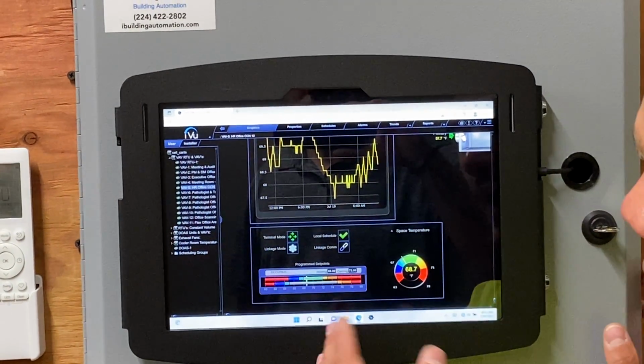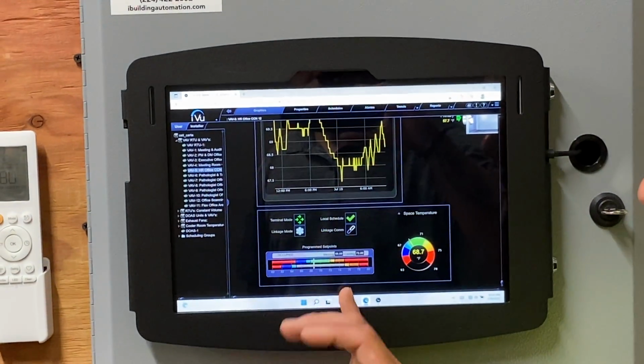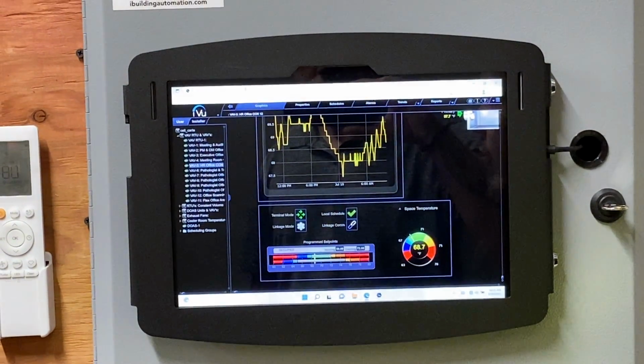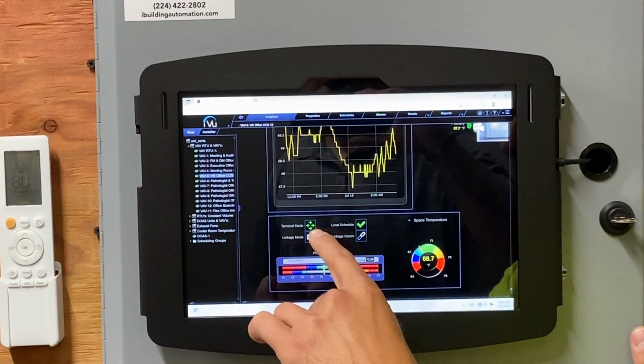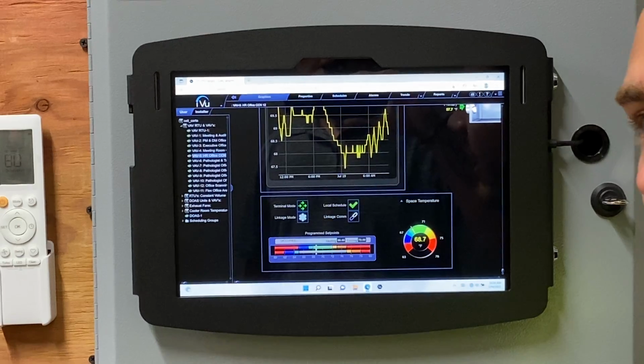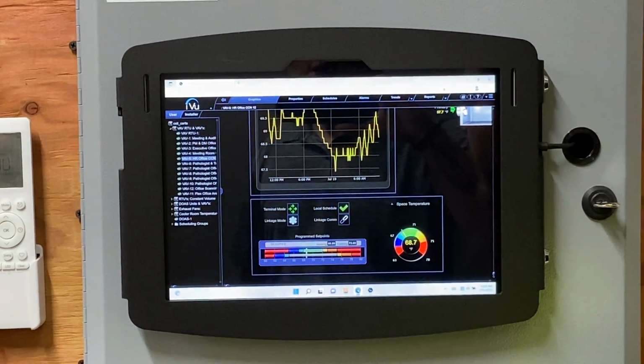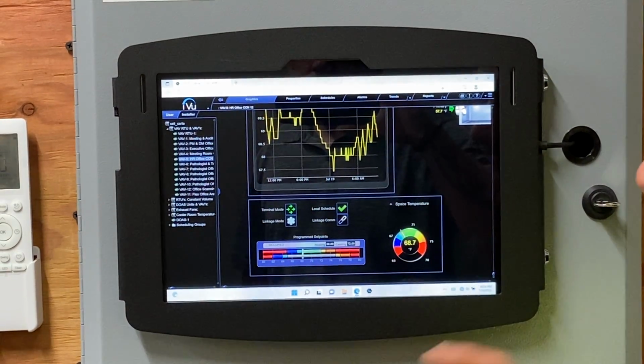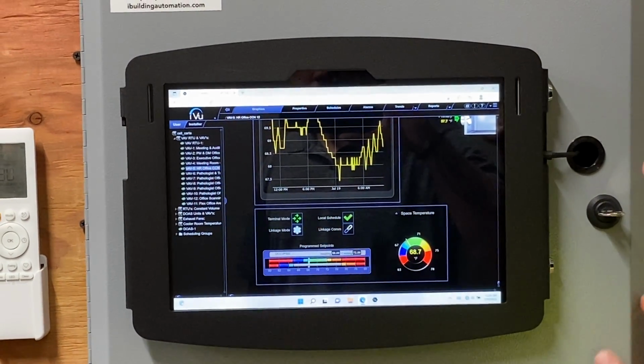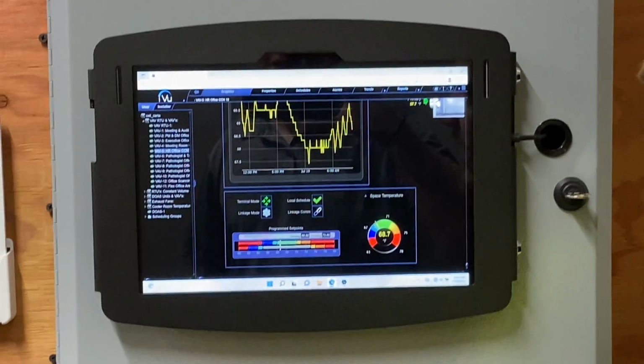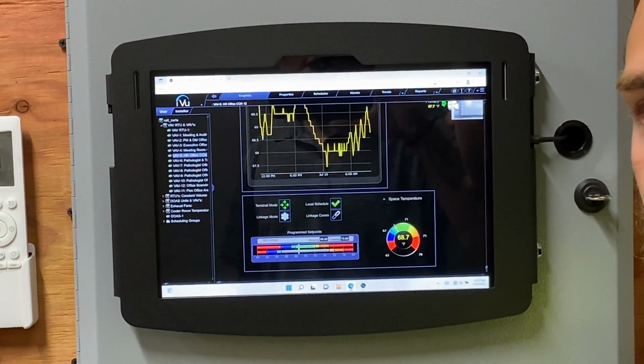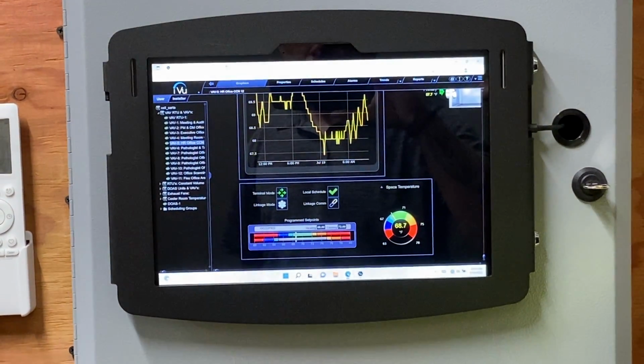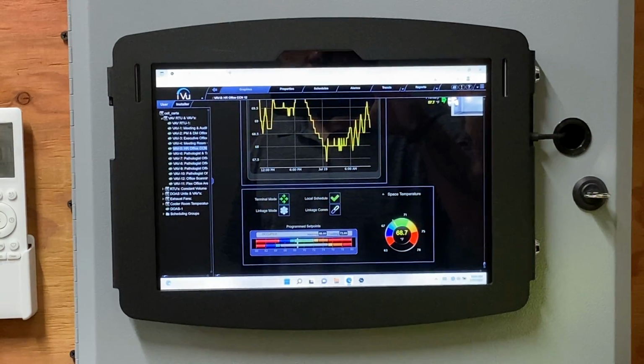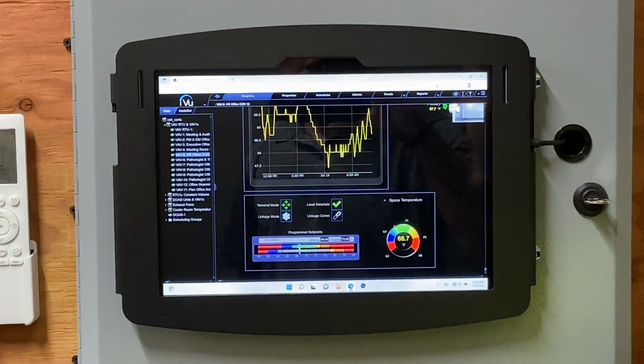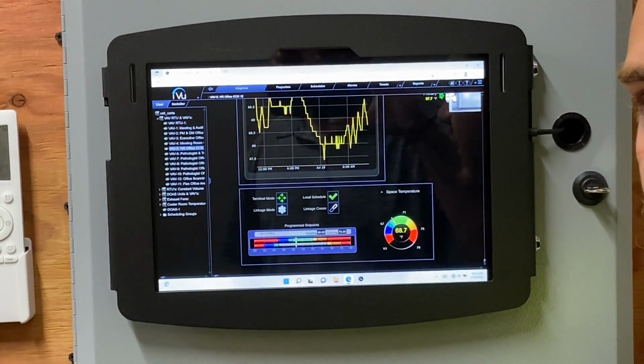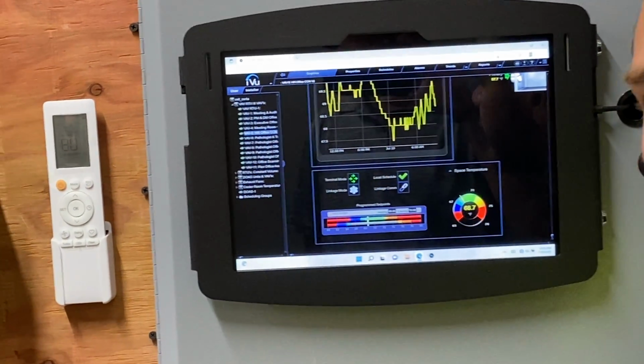So optimally what you're going to want to see is 69, 70, 71. That's that middle area. During those periods, you're not going to be heating or cooling. You're just going to be showing a terminal mode with these arrows on it, indicating that we have a fan-only mode. Until we go a degree below or a degree above, we're not going to heat or cool. And we have a 4-degree dead band between 68 and 72 per code. We're not going to do something like 68 and 70. That's just too tight for the unit to respond. So 4 degrees is our split no matter what. So if we did change it come winter time and 68, 72 is not enough, we did 70, 74, we always have to have a 4-degree split between our heating and cooling set points. Otherwise things are cycling on and off too much, and it can't do that.